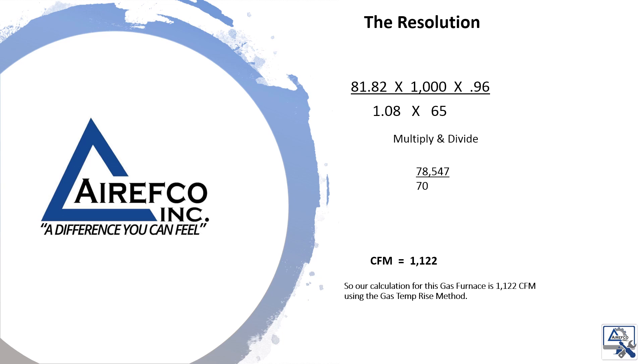Our resolution to this equation is to take our 81.82 cubic feet per hour times 1,000 BTU heat content times 96% efficiency of the furnace, divided by 1.08 times our temperature rise of 65 degrees. When we multiply and divide that out, our calculation comes out for this gas furnace to be 1,122 CFM using the gas temp rise method.